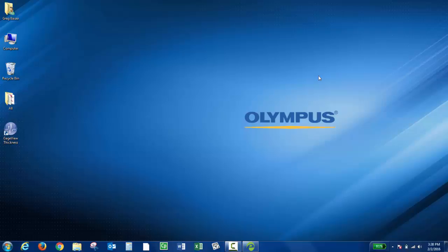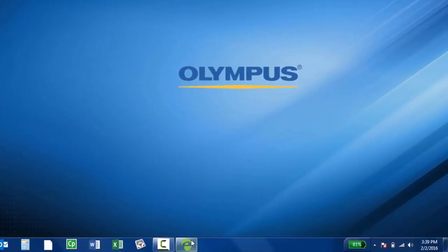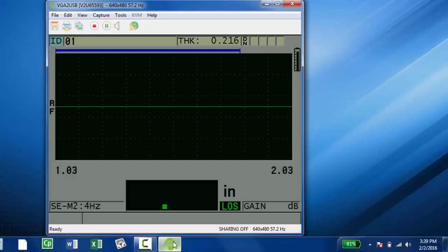In this video, I would like to show you how to connect the Olympus 38DL Plus to the GageView Thickness program through a USB cable. The first thing you want to do is verify the communication settings on the instrument. So I'm using a VGA to USB adapter, so you can see the screen of my instrument.